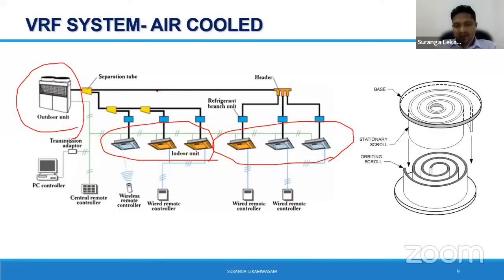You don't need to run separate pipes for each of the indoor units, because here the technology is different, where your expansion devices are inside the indoor unit, right? That's the difference. That's why you can run a single set of pipes to each and every unit. This is again a very commonly used system in the industry. Some of the clients are not willing again to have VRF, right? It's strange sometimes. I have some experience with a very leading hotel operator. They said that they don't need VRF because your expansion device is within your indoor unit, and they may give some expansion noises, right? The customers are complaining. So that kind of thing is also there, but typically that is a good system for you to practice.